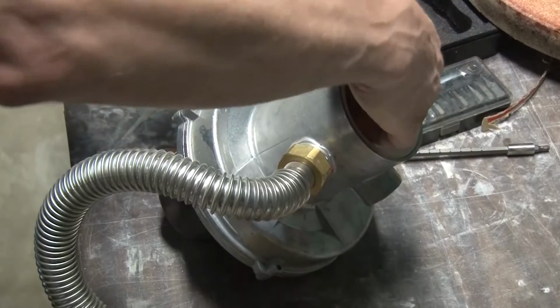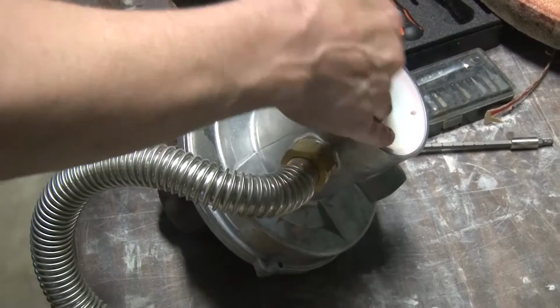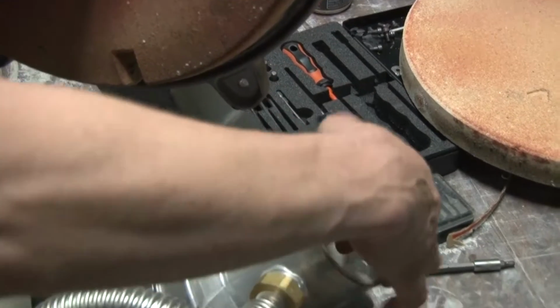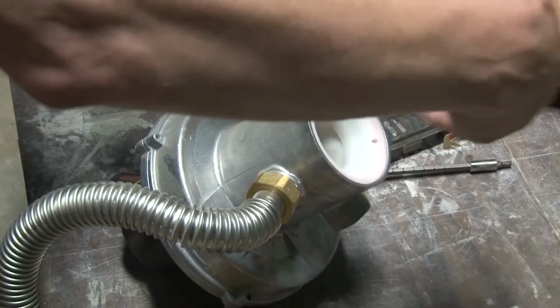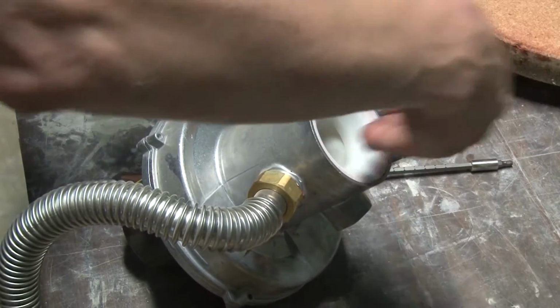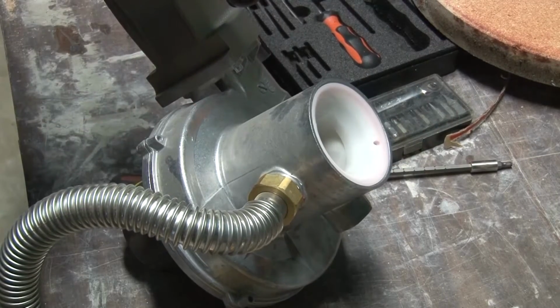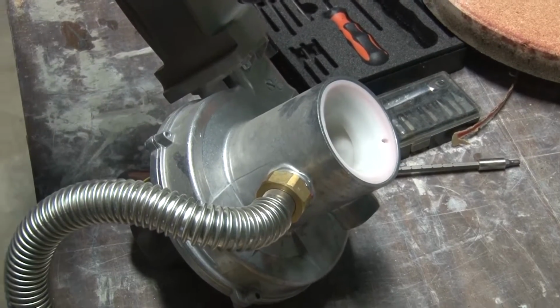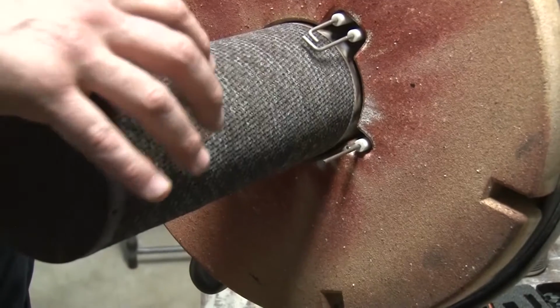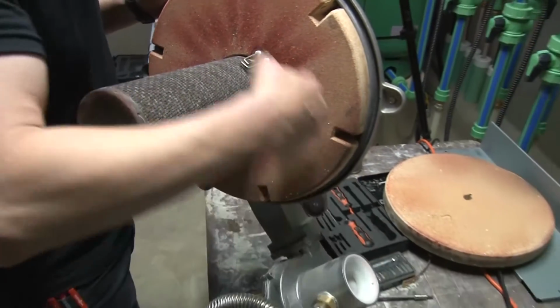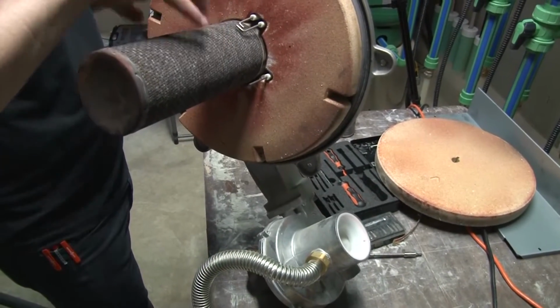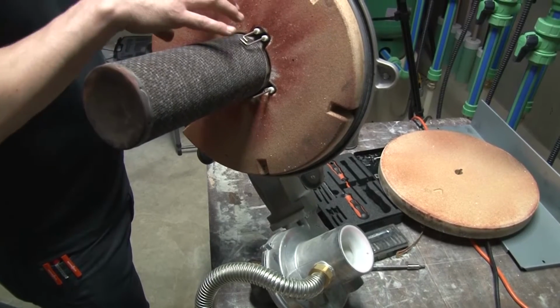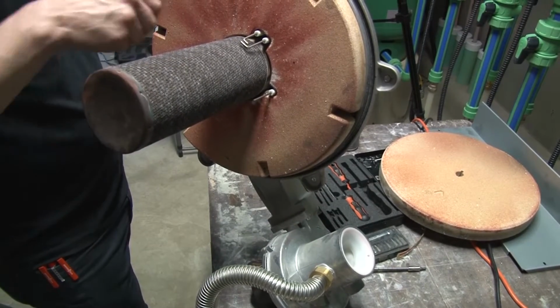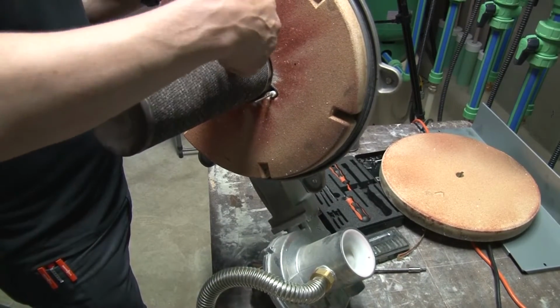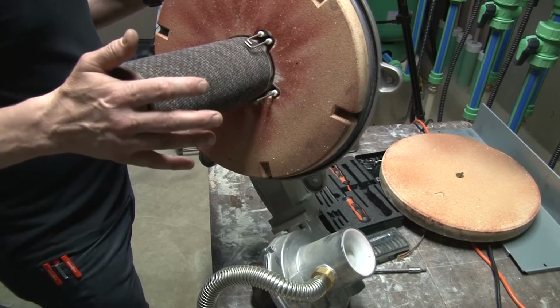So if this is really fouled up, and I put my finger in there and pull a lot of debris out of there, then I know that there's a lot of contamination of combustion air coming in. That's going through the burner and it's coming out on the catch-all here. This little mesh is the burner mesh. And of course, if this is dirty down here, this is going to be fouled up as well on the burner. So I'd have to pull it out and we'd have to use a vacuum or whatever and vacuum both the inside and the outside of that little burner tube.